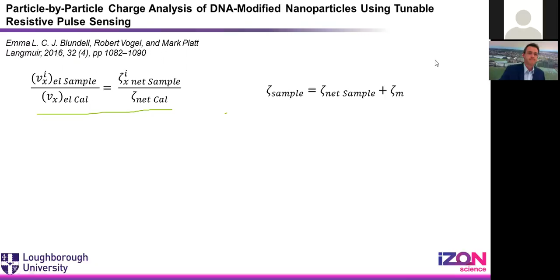So to account for this and build in a bit more flexibility, we're going to calibrate the pore by making a measurement of the particle's velocity at different voltages. This allows us to then come back and make a measurement of our sample under different conditions under a fully calibrated pore. So I changed the voltage and I measured the velocity, 1 over t, for my calibration bead as it goes through.